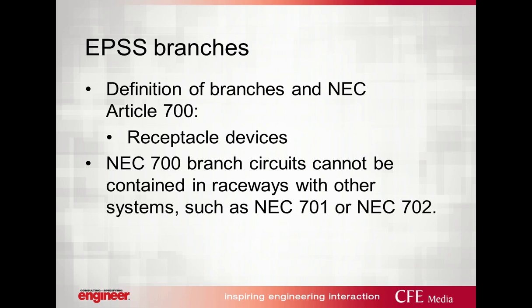So this is in discussion on the application of branch circuits as it applies to NEC 700. I think one of the misconceptions a lot of times is that we see receptacles placed on emergency life safety circuitry. The reality is this: as a designer, I want to guarantee, no matter what, that emergency distribution system, all the way down to the branch circuit connection to the equipment that's operating, is going to operate properly. Nowadays, we get into branch circuit requirements with SPDs all the way through the distribution system of Article 700 and 701 requirements. But back to that receptacle, in the past, there were a lot of designers that would put receptacles because somebody said, hey, I need to make sure that my equipment operates in an outage. So they would put receptacles on emergency power.